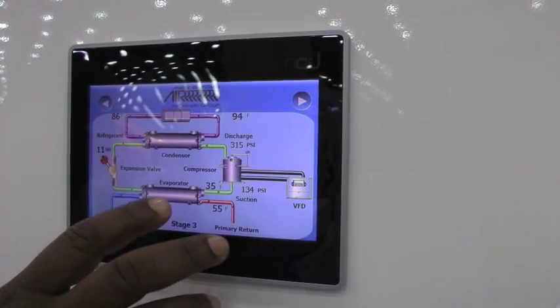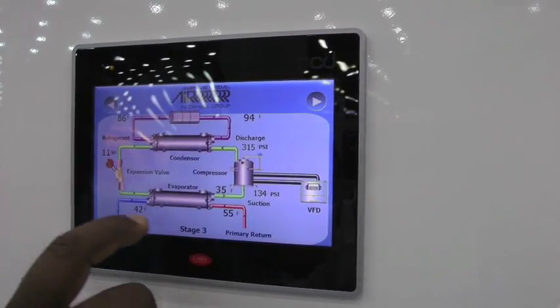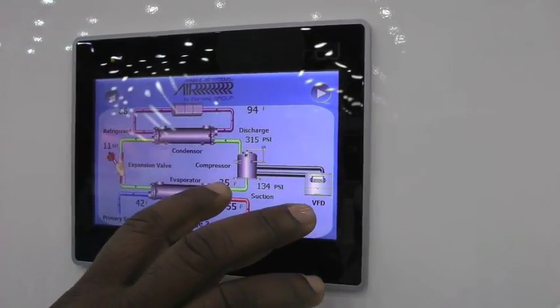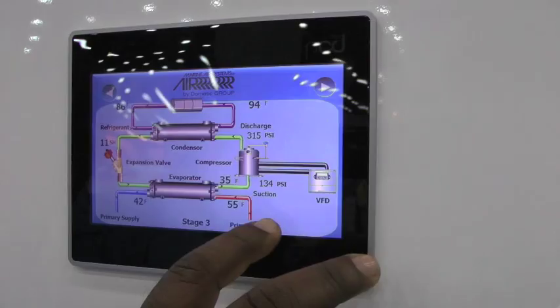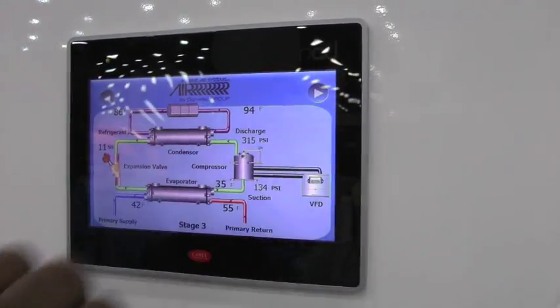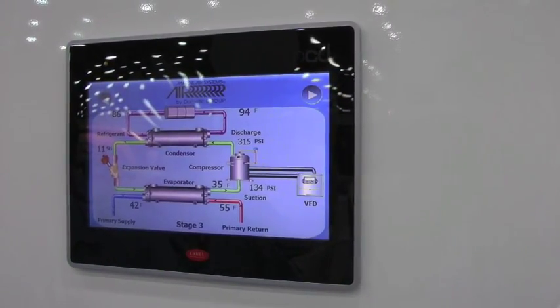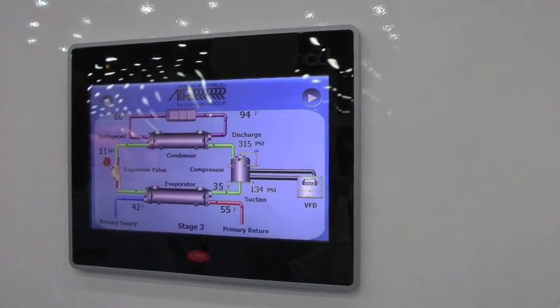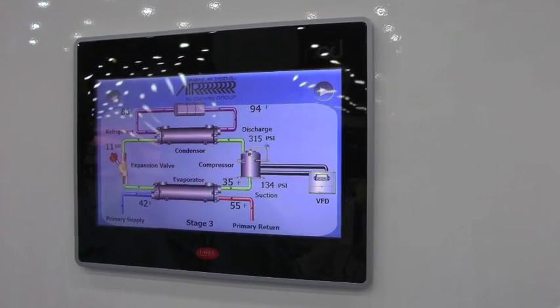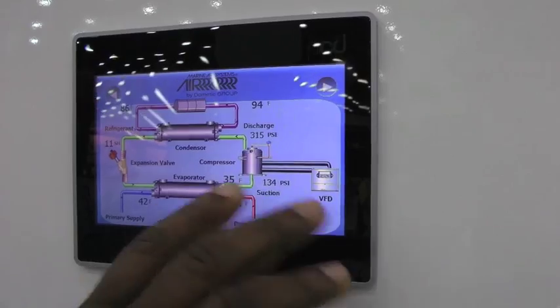Your refrigeration circuit, like I mentioned, is here as well. We monitor the suction pressure, suction temperature, and discharge pressure. Those values indicate whether or not the system is running properly, so there are baselines there.